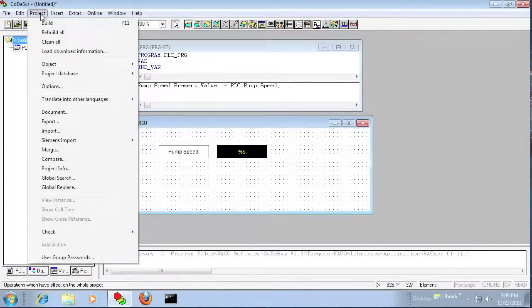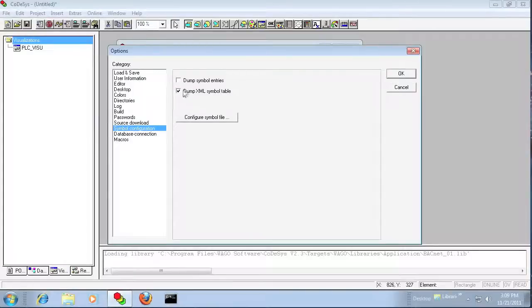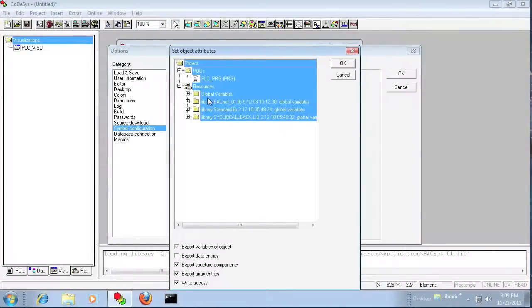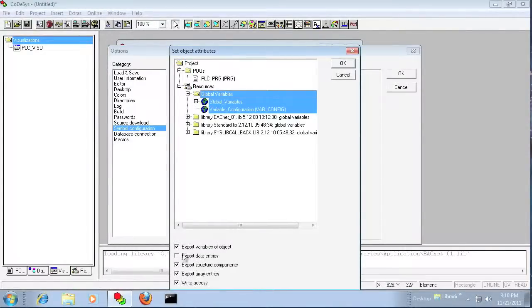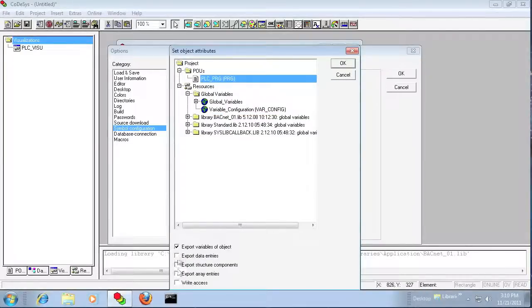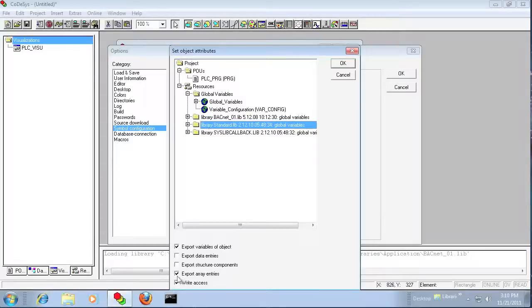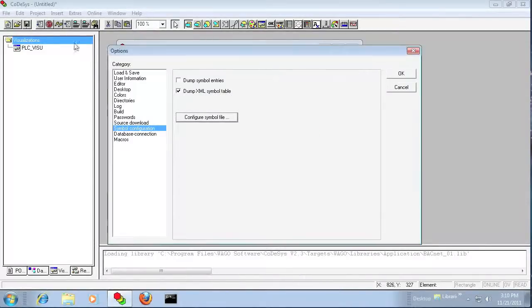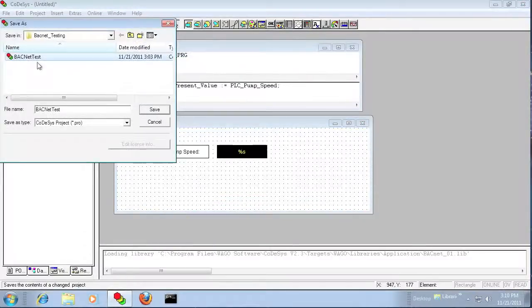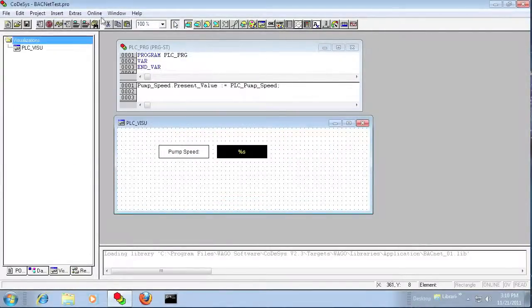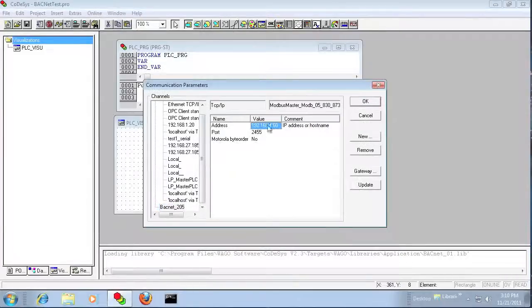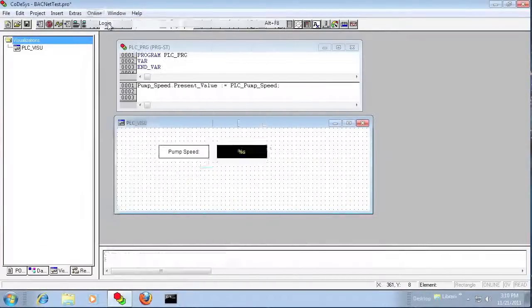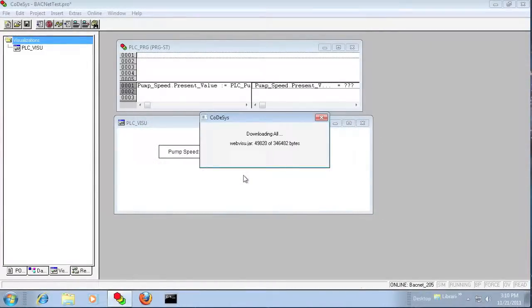At this point, we want to create the XML object, which dumps the objects to a file that the configurator program can read. For the global variables, I'm just going to export the data entries and go with the defaults on the BACnet IP library — it's going to need write access. Go ahead and save that off, and when you build the project it will create the XML file automatically when you download.